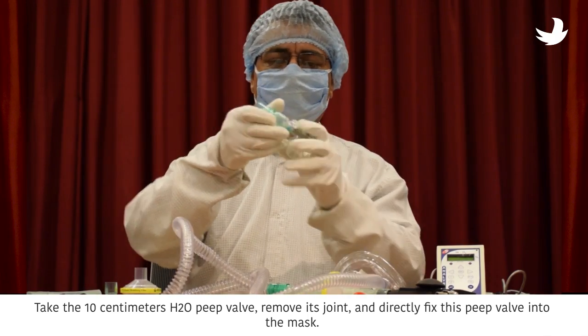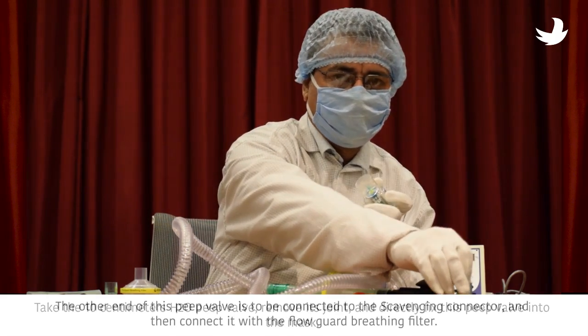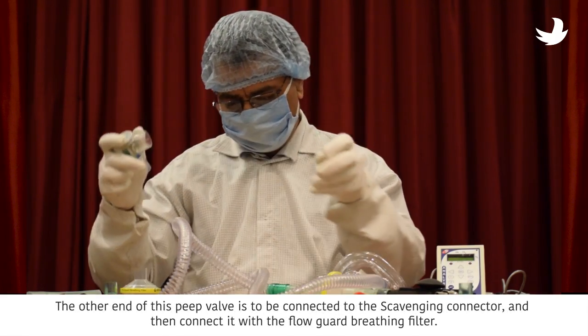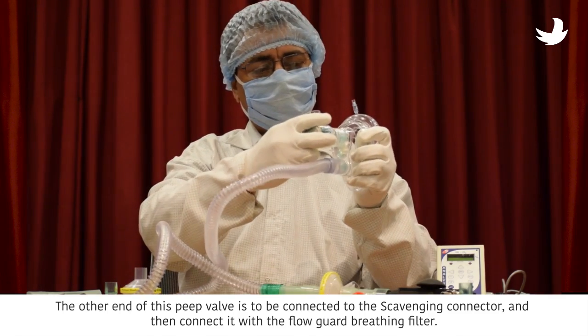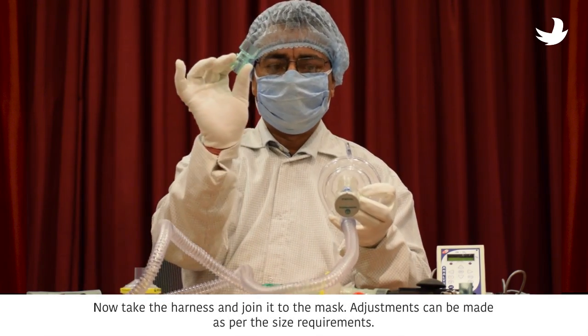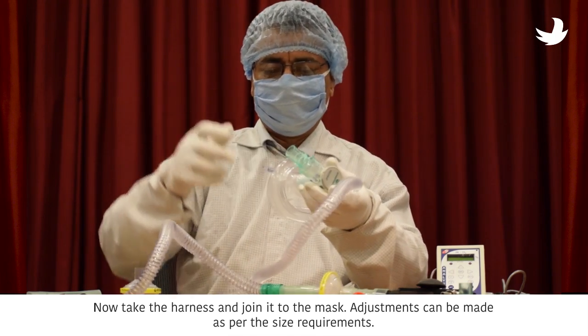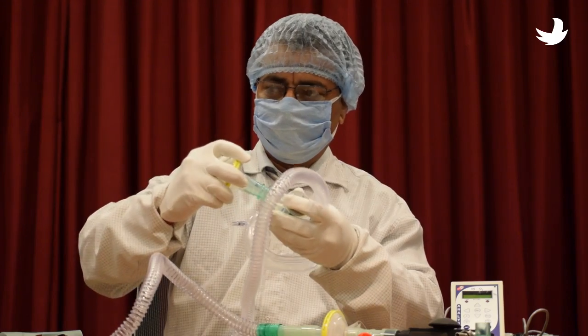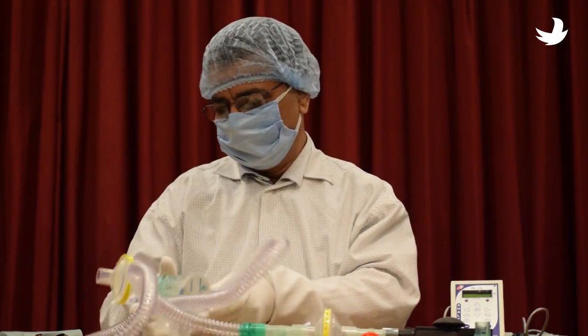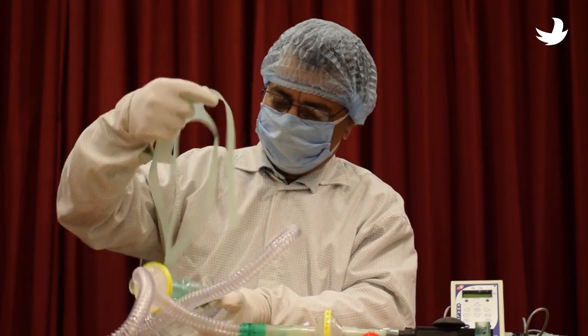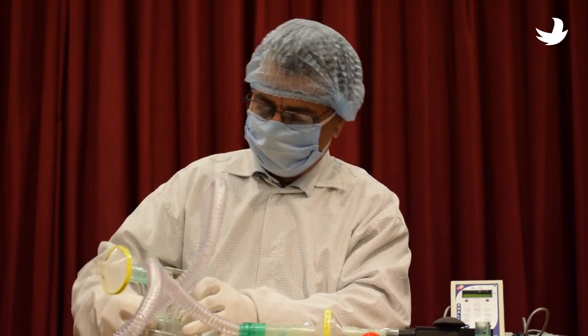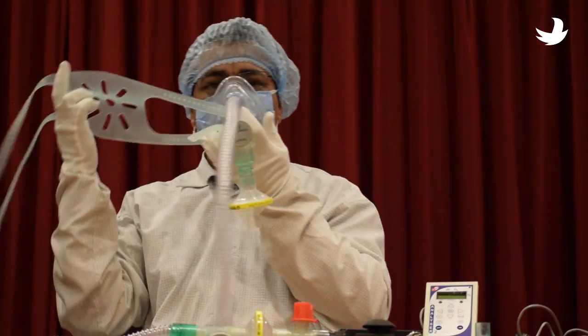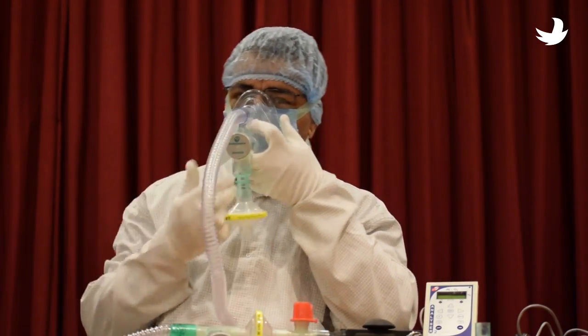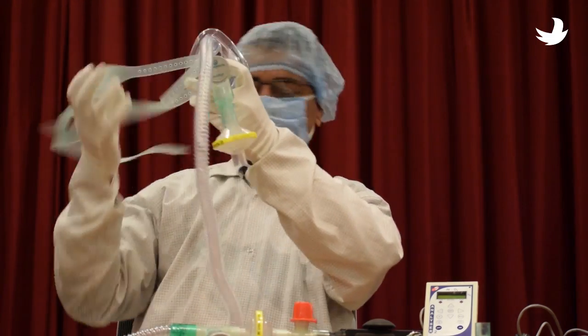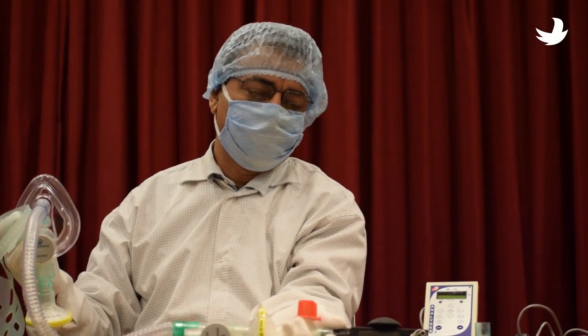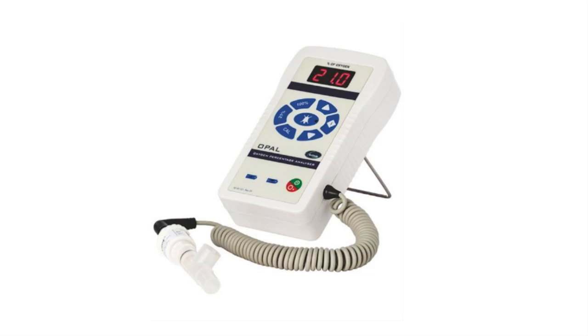Take the 10 cm H2O PEEP valve, remove its joint, and directly fix this PEEP valve into the mask. The other end of this PEEP valve is to be connected to the scavenging connector and then connect it with the flow guard breathing filter. Now take the harness and join it to the mask. Adjustments can be made as per the size requirements. So this is the complete assembling of the patient circuit with the Oxy CPAP P12 device. Remember that the 10 cm H2O PEEP valve should be connected to the patient's mask. The breathing filter must be changed at least once in 24 hours.